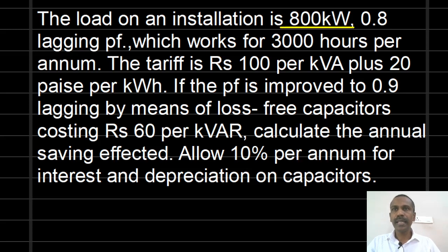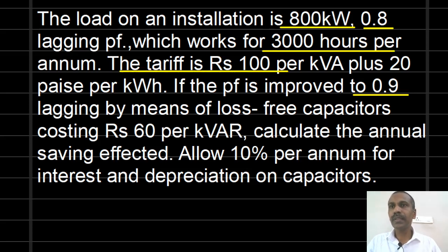The load is 800 kilowatt. Its initial power factor is 0.8 and we are going to improve the power factor up to 0.9, and this load works for 3000 hours per year. Here the tariff is given. The term tariff means the cost of electricity bill. It is rupees 100 per kVA plus 20 paise per kWh.